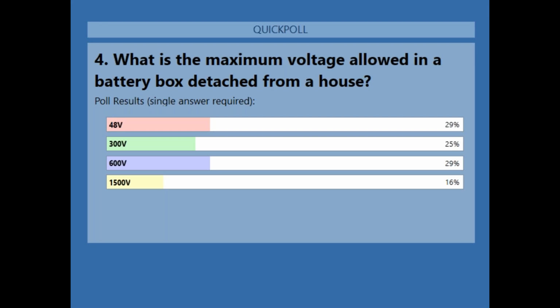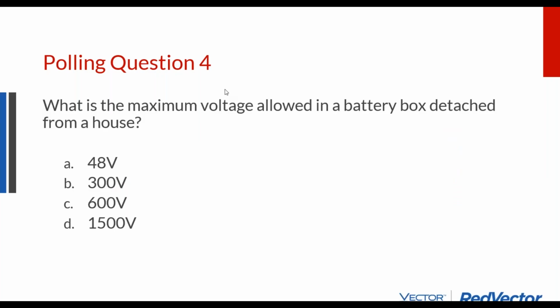Now, most battery systems are at 48 volts, but not all. The Tesla Powerwall, for example, and there's a popular solar inverter company called SolarEdge, and they've partnered with LG, and they make a higher voltage battery. A lot of commercial batteries are at higher voltage too, for the reasons we just discussed. The higher the voltage, the lower the amperage. Traditionally, the battery inverter industry is at this 48 volt platform. But the problem with that is the lower your voltage, the higher your amperage, and the thicker your battery cable.